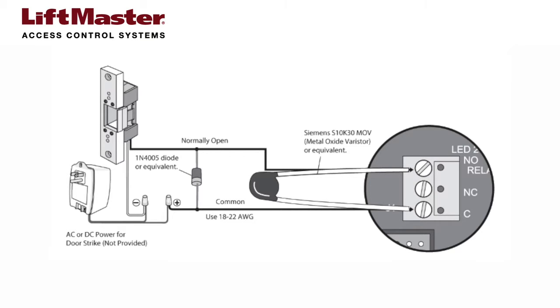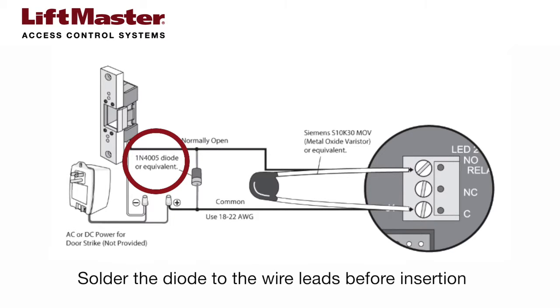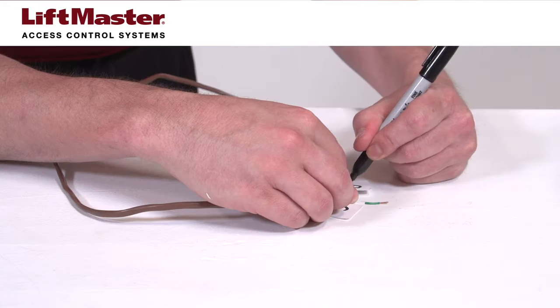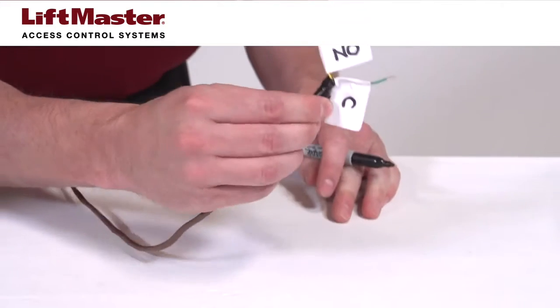If the door strike uses a DC power transformer, connect a 1N4005 diode to the common and normally open terminals on relay 2. It's best to solder the diode leads to the wire leads. Label the other end of the wire according to the connection.